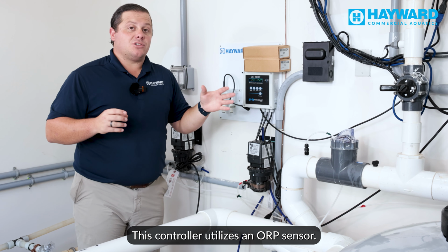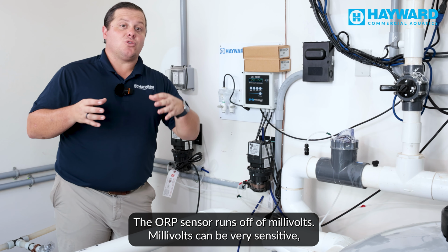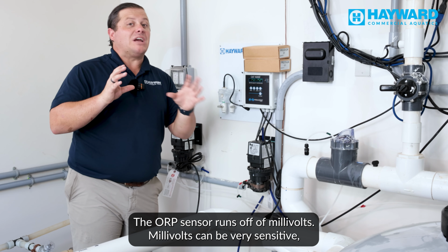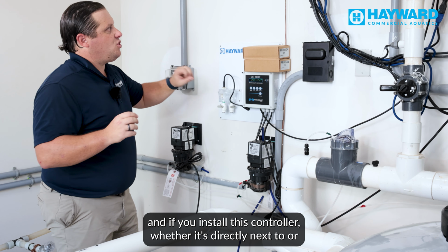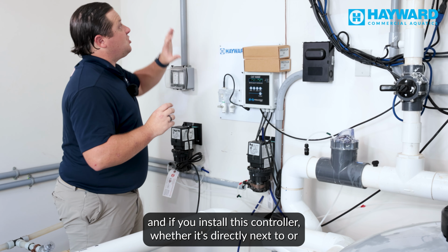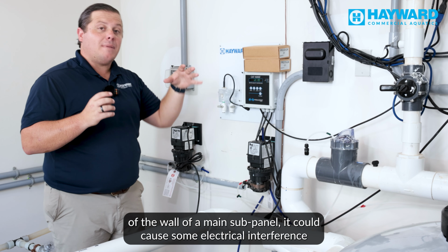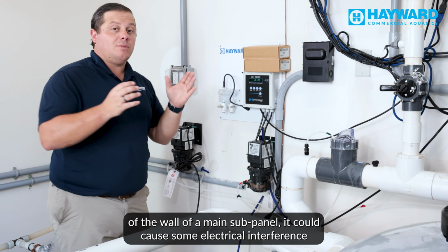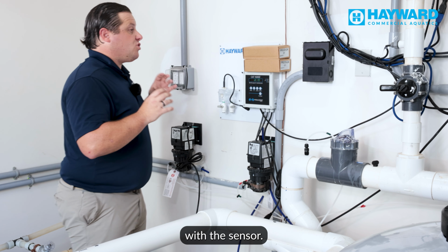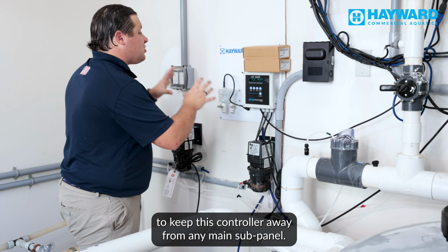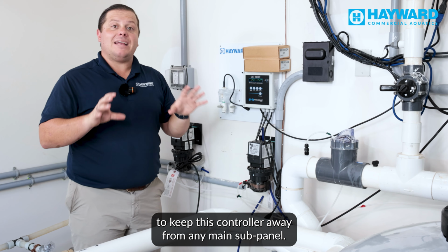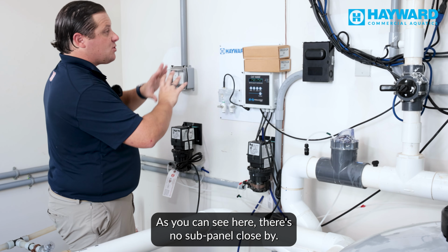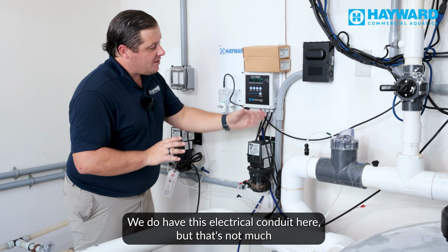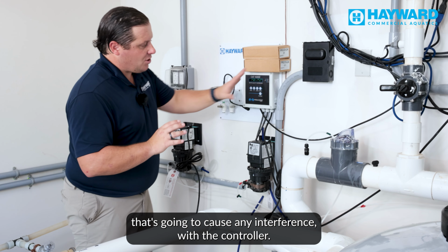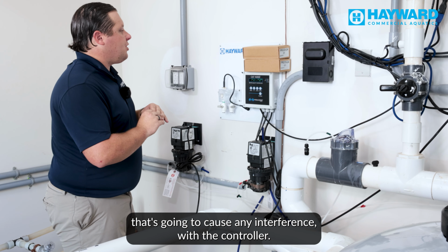This controller utilizes an ORP sensor. The ORP sensor runs off of millivolts. Millivolts can be very sensitive, and if you install this controller directly next to, or on the opposite side of the wall from, a main sub panel, it could cause some electrical interference with the sensors. So you always want to keep this controller away from any main sub panel. As you can see here, there's no sub panel close by. We do have this electrical conduit here, but that's not going to cause any interference with the controller.